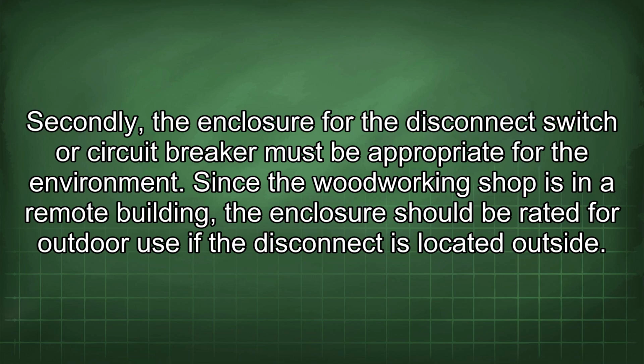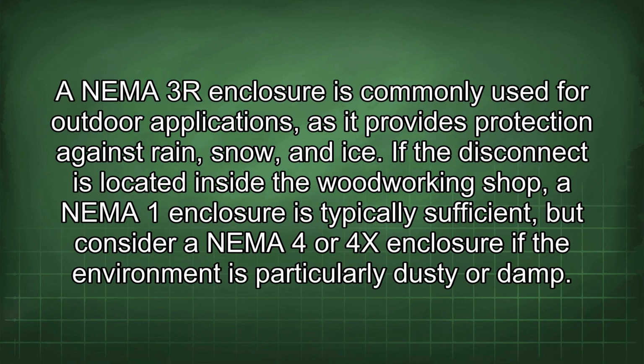Secondly, the enclosure for the disconnect switch or circuit breaker must be appropriate for the environment. Since the woodworking shop is in a remote building, the enclosure should be rated for outdoor use if the disconnect is located outside. A NEMA 3R enclosure is commonly used for outdoor applications, as it provides protection against rain, snow, and ice. If the disconnect is located inside the woodworking shop, a NEMA 1 enclosure is typically sufficient, but consider a NEMA 4 or 4X enclosure if the environment is particularly dusty or damp.